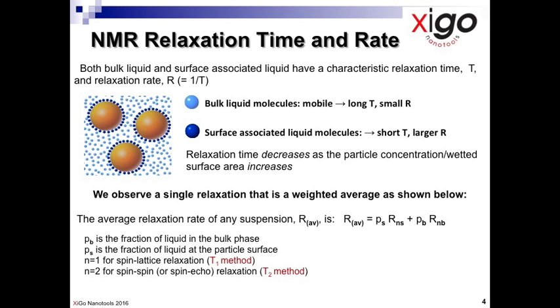In part one, we defined two liquid domains: liquid on the surface of a particle and bulk liquid far away from the particle surface. The liquid molecules far away from the particle, shown as light blue, are much more mobile and relax slowly, on the order of two to three seconds — the relaxation time T is long and so the rate R, the reciprocal, is small. However, liquid molecules on the particle surface, shown in dark blue, are restricted and relax more quickly, on the order of only 0.5 to two milliseconds, resulting in a much shorter relaxation time and a larger relaxation rate R.